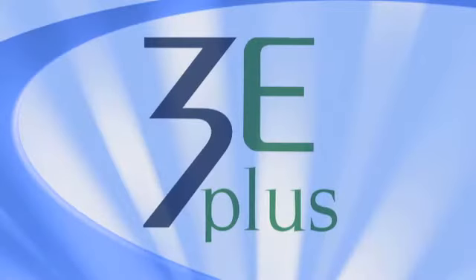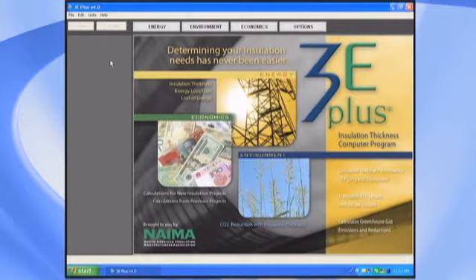I'm here today to talk about NAIMA's 3EPlus program. 3EPlus is a computer program that will allow you to calculate heat loss and heat gain in a piping or insulation system. 3EPlus is a simple program. It does a steady state, one-dimensional heat loss calculation of a piping or equipment system.